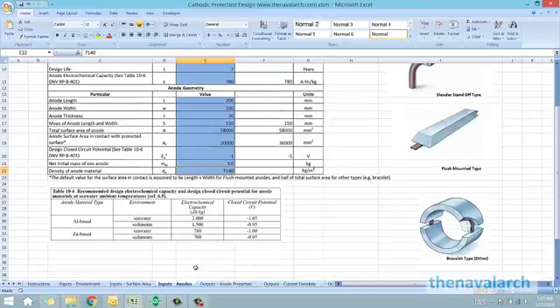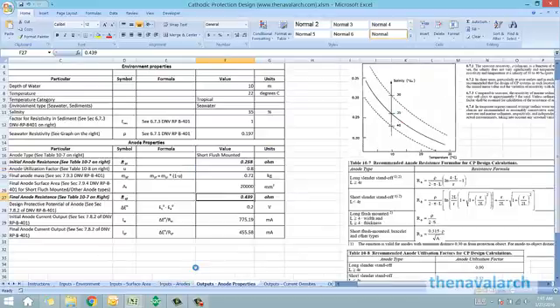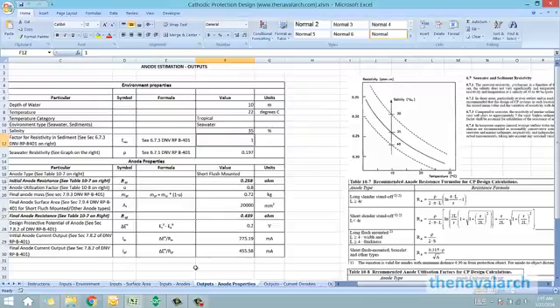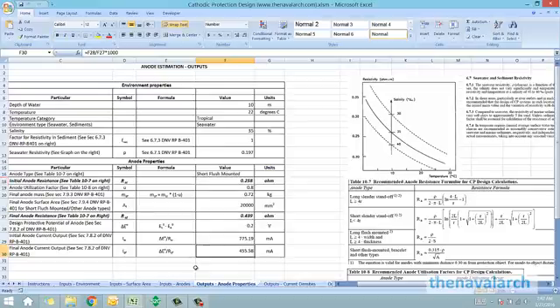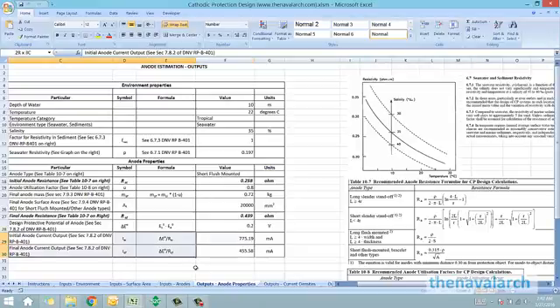Once the user has given all the inputs, we go straight to the outputs. The output spreadsheet calculates the resistivity of the seawater and the resistance of the anode — both initial and final resistances — and from these resistances it calculates the initial and final current outputs of a single anode. These are the anode property outputs which the spreadsheet generates.